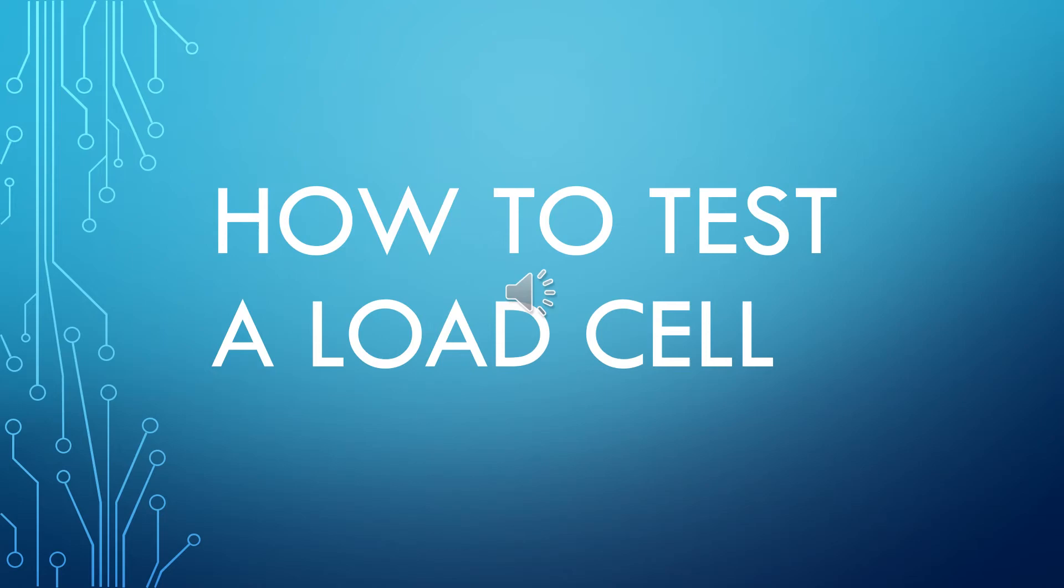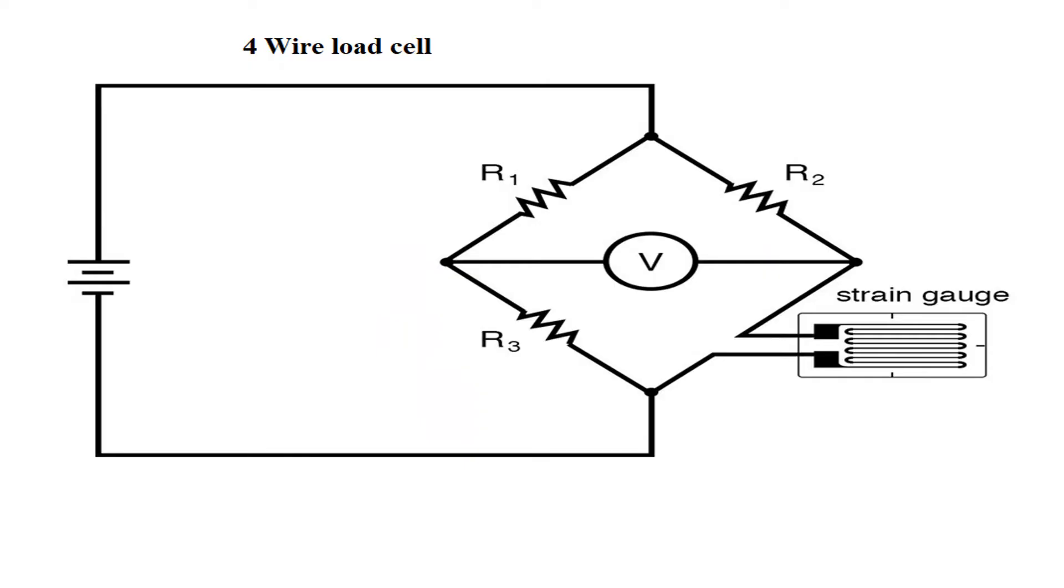How to test a load cell. The load cell is connected to the famous Wheatstone bridge circuit. The strain gauge is the sensing element in the load cell that converts the pressure or weight to resistance. In this video we will learn how to test a four wire load cell.